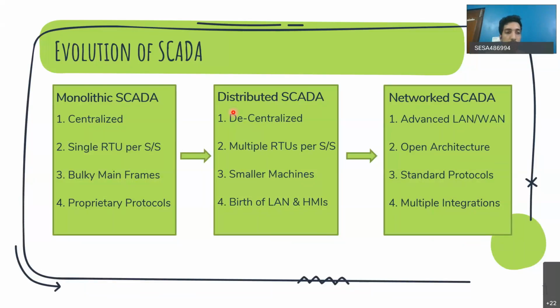And there was only the feasibility of a single RTU per substation. So you remember, RTU is remote terminal unit. That is the intelligent device that facilitates all these things, control and monitoring. So this drawback was there initially, only one RTU per substation. And then on the control center side, there were very bulky mainframe machines which were huge in size, so managing them was not very easy. And the protocols of communication between the RTU and the control center were proprietary in nature. So it was all vendor specific. So we had to run around to different vendors for different issues.